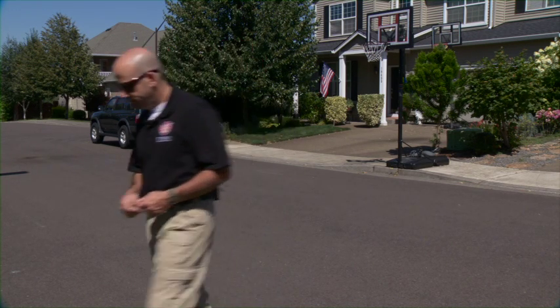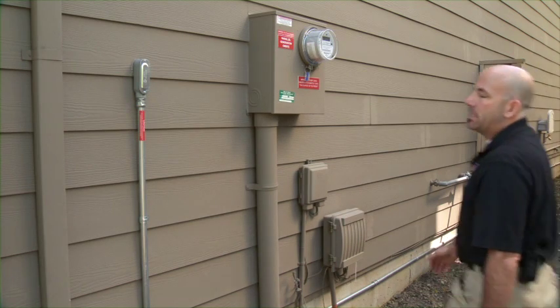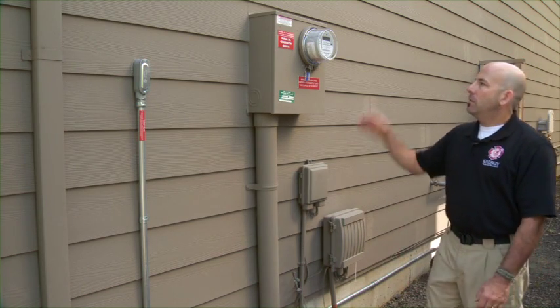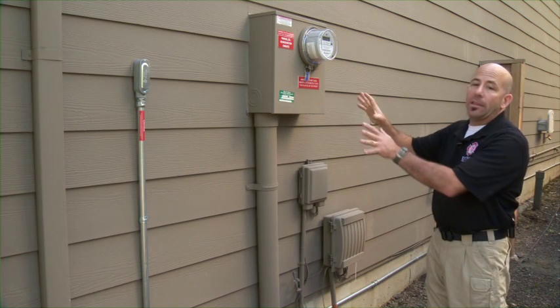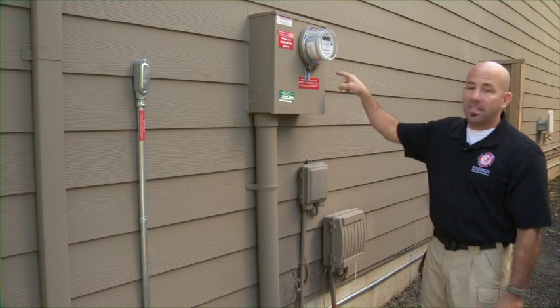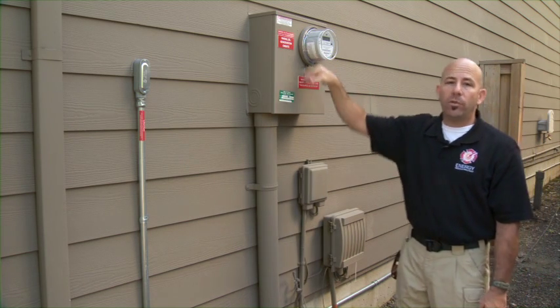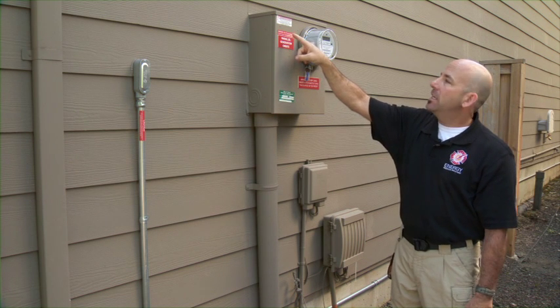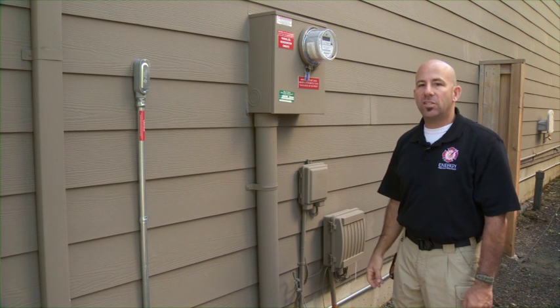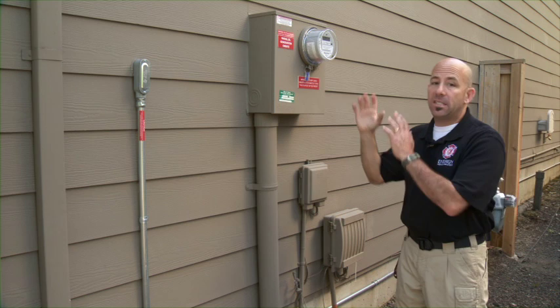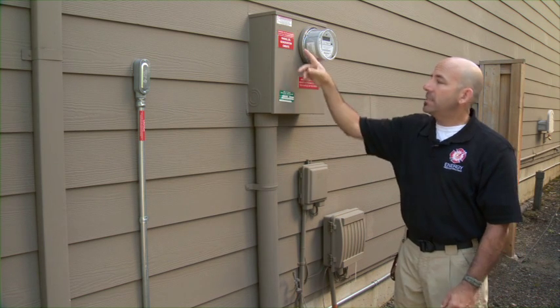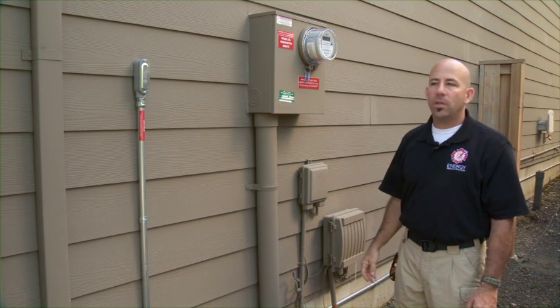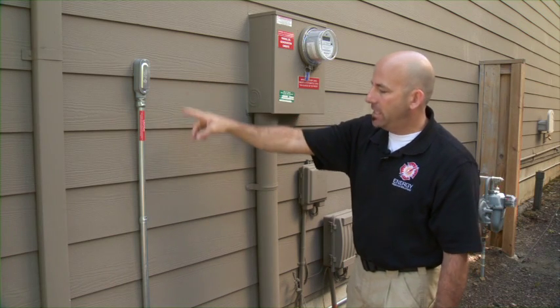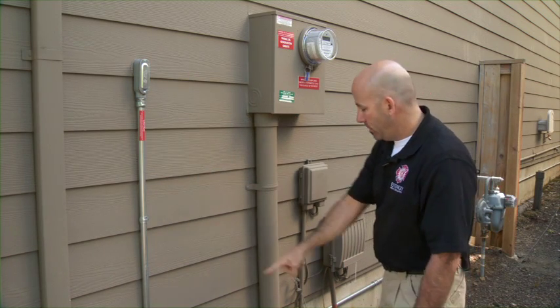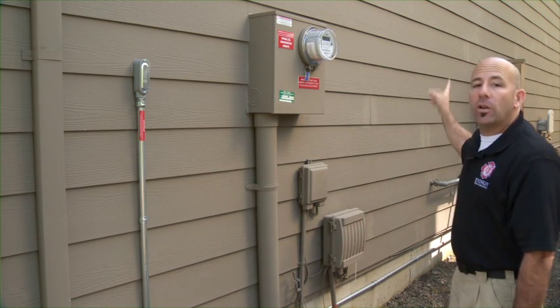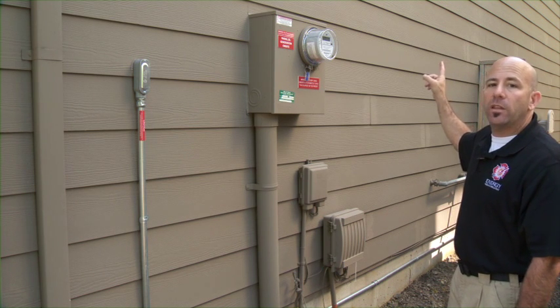Let's go. All right, so we're on the delta side of the structure. We've got the main meter here. However, there's not the circuit breaker panel. That looks like it's going to be inside the garage. But there are some labels here. One of them says warning, dual power sources. Second source is a photovoltaic system. So that says it right here for us. A lot of times these red labels will be enough for us. But the other thing that's present here is this conduit that's going into the garage that continues on. We're going to go and look for that because that's going to tell us where the array is.